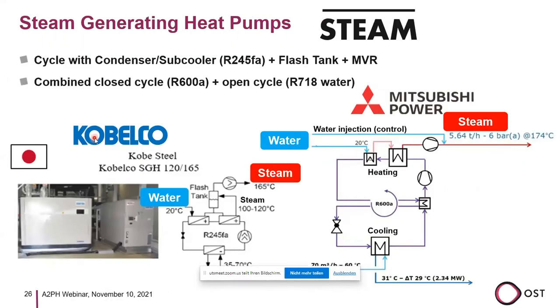Kobelco, which was mentioned before, is using such a kind of system. They have a closed cycle heat pump with a screw compressor here. Then the water is in an open loop with a subcooler, then another heat exchanger producing steam, which goes into a flash tank. Saturated steam is recompressed to higher pressure steam.